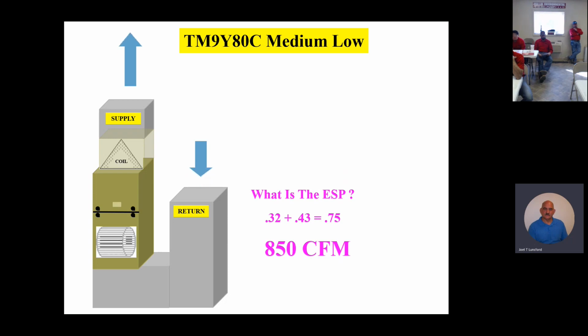Now, let me ask you cats a question. Where's the problem on this system here? Is it supply or return where we have the problem? Yeah. You got 0.43 inches on return. That's a lot of static on the return. Guys, put this in your back pocket. Again, one of those little things that I like you to keep your brain engaged on. You want about 60 to 70% of your static, the energy of that fan doing the blowing, not the sucking. Because the supply side is the high energy side of the fan, and we want about 60% or 65% or so of the energy of that fan moving the air on the supply side.